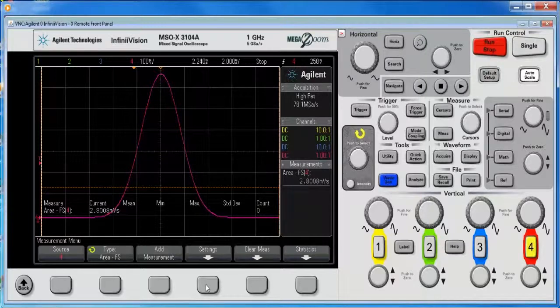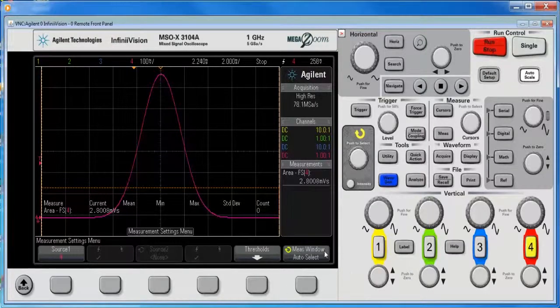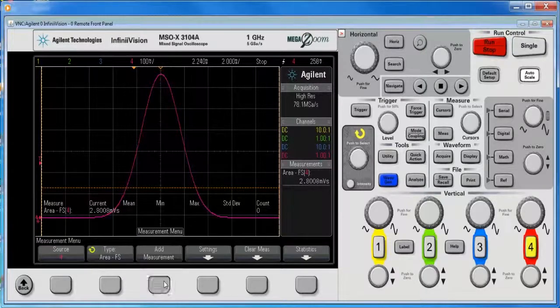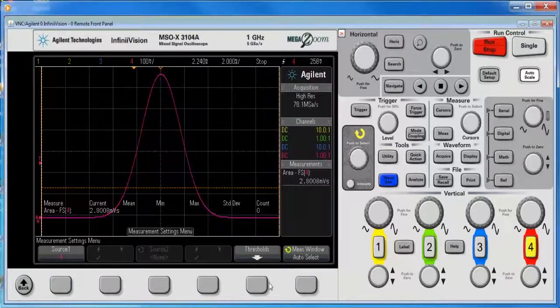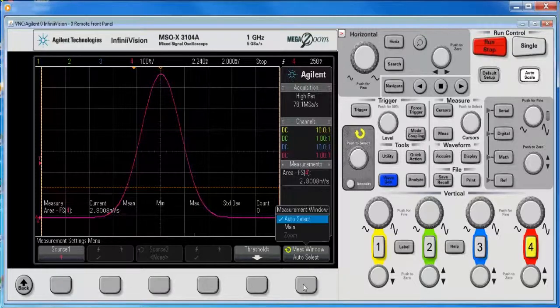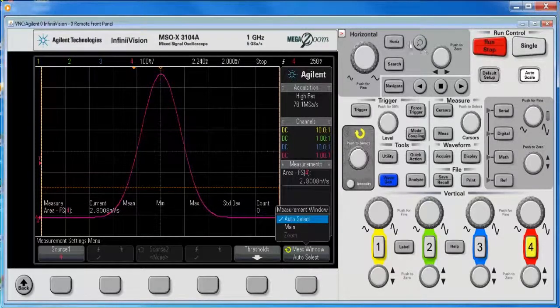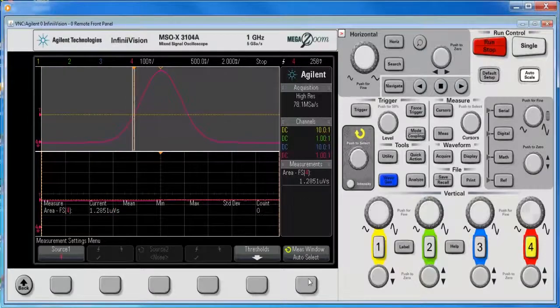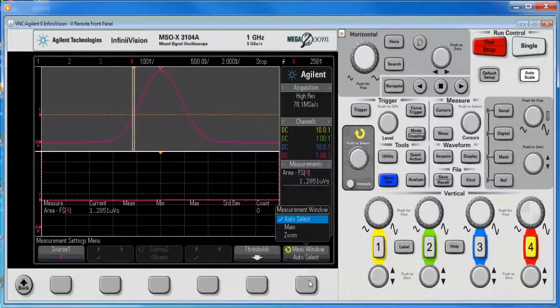So, one way to achieve this, if I go to settings on the measurement, so measure to settings. I can use the measurement window auto select and gate it to the main or the zoom window, but I do have to turn on the zoom window first before I get that option. So I can go to zoom.